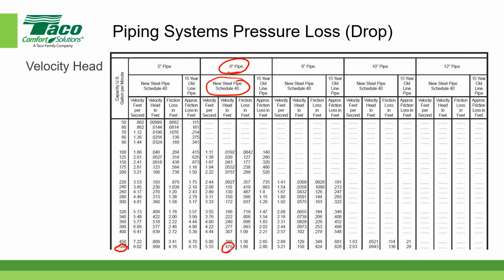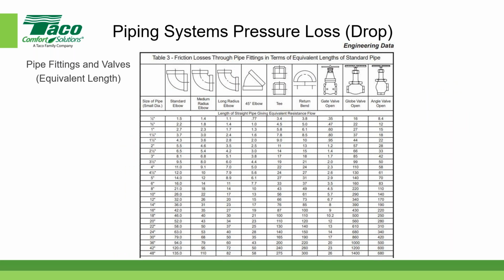Now, the friction loss happens to be 1.66 feet per 100 feet. And that is done not by a straight calculation, but through experimentation over a period of time that manufacturers have published data about their piping. So those are the three values that we're most interested in today: the velocity head, and the pressure drop in feet per 100 feet. Okay, let's continue along here.